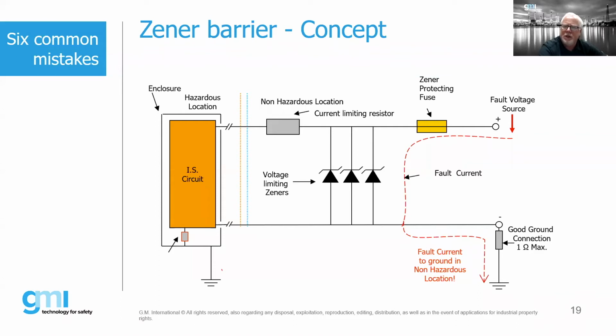Once the voltage achieves a certain level above the threshold, those Zener diodes open up. They allow any of that excess voltage to pass through to ground. Notice on the right-hand side that with Zener diodes we must have a good ground connection, typically 1 ohm or less maximum of resistance. So that's typically how our Zener diodes will act. Now, obviously, during a situation where we have a high inrush current, we have our current limiting resistors, and we also have a fuse.